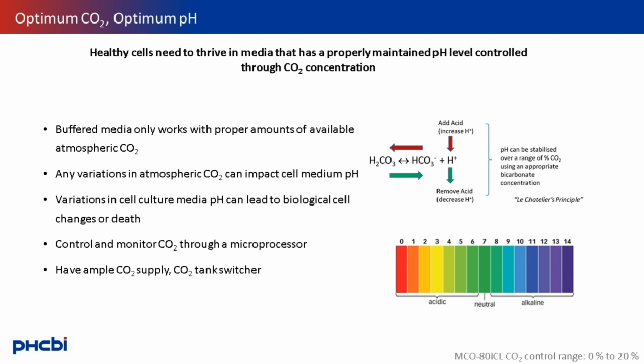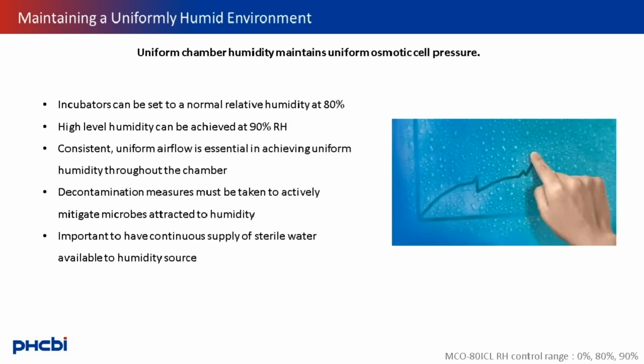An automatic tank switcher can also ensure that there is plenty of CO2 readily available for use. Humidity must be consistent throughout the entire incubation chamber in order to maintain the proper osmotic balance a cell needs to thrive. Humidity levels can be set to 80% humidity for normal humidity conditions. The humidity levels can also be set to a 90% relative humidity to facilitate an elevated humid environment.